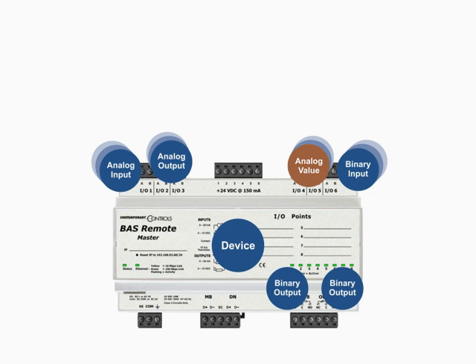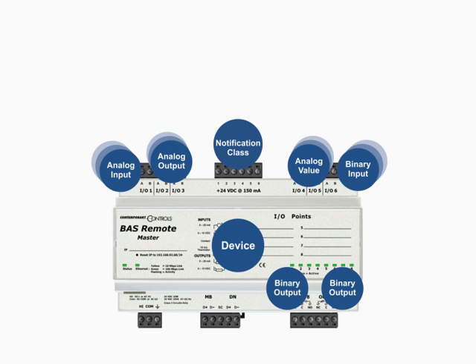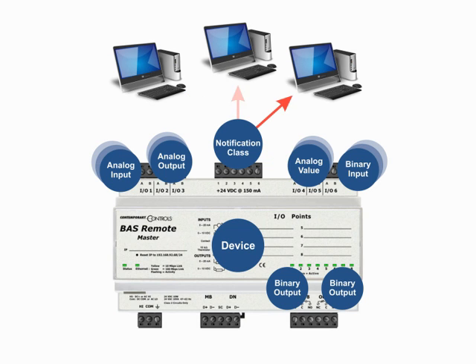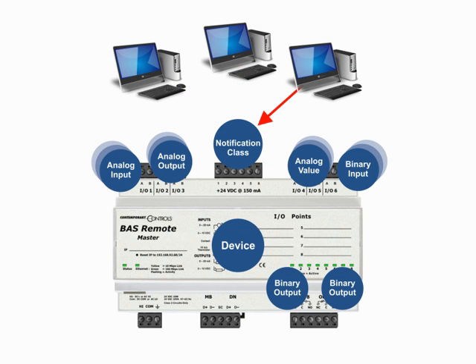Using a notification class object, the object determines when and where the alarm is reported. An event notification message is sent to one or more alarm recipients. Notifications await acknowledgement by the recipient if they are confirmed notifications.